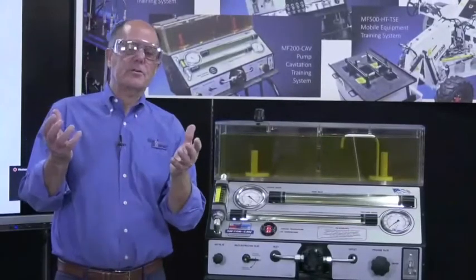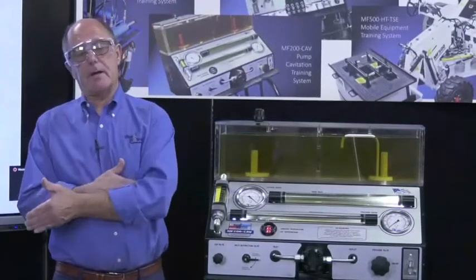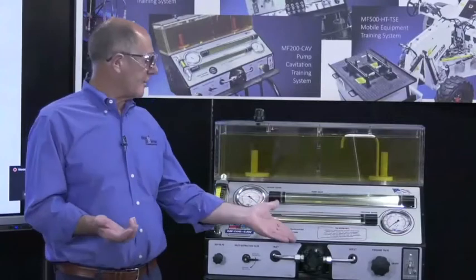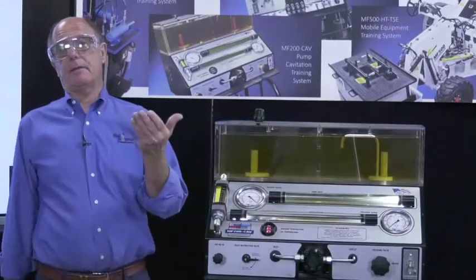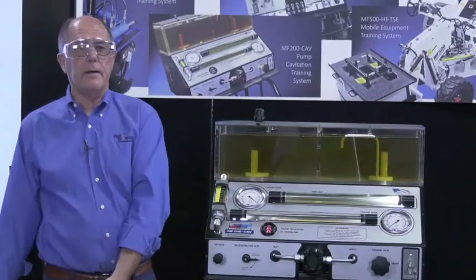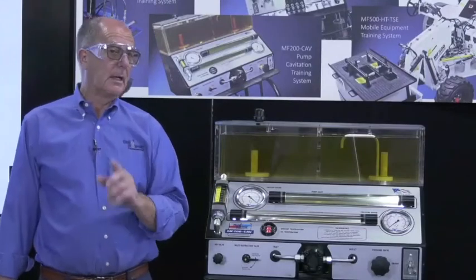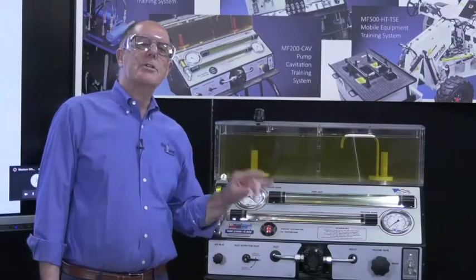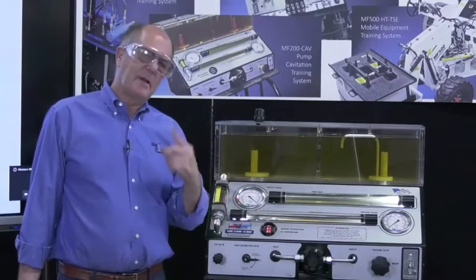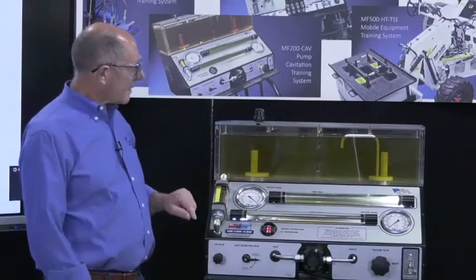If you read a book on inlet restriction, it'll say the lower the inlet restriction, the better. Well, that's true. If the manufacturer of this pump says the max is 8, it can be anything below 8. It can be 1. But lower is not better if I don't have a point of reference. Let me show you why. So let me start that again.